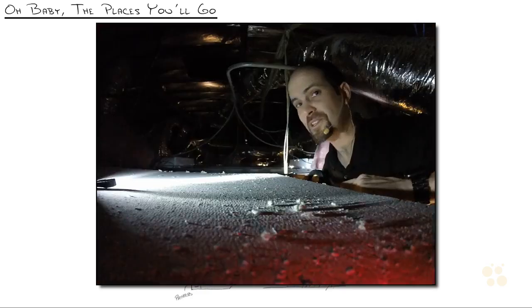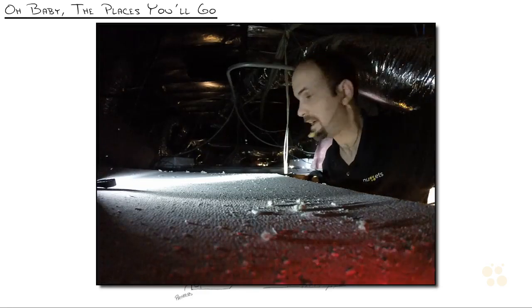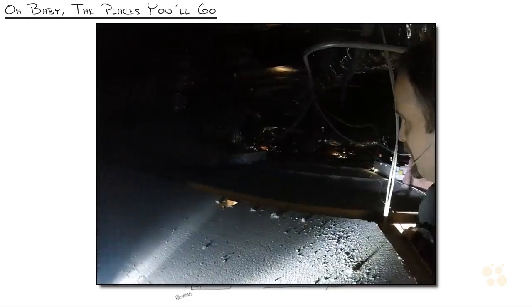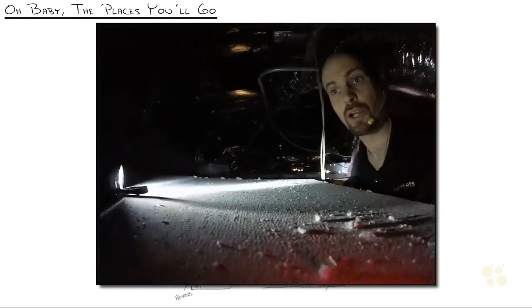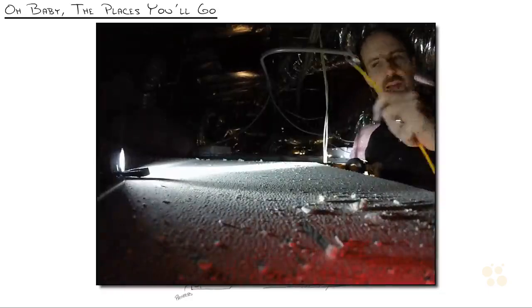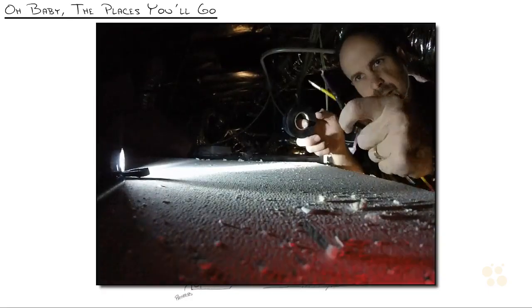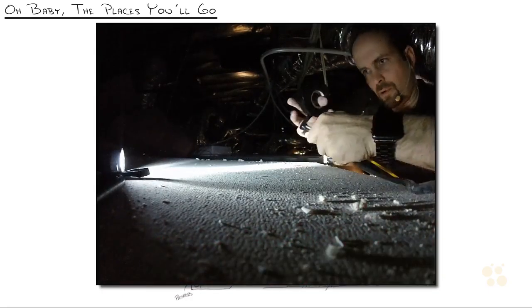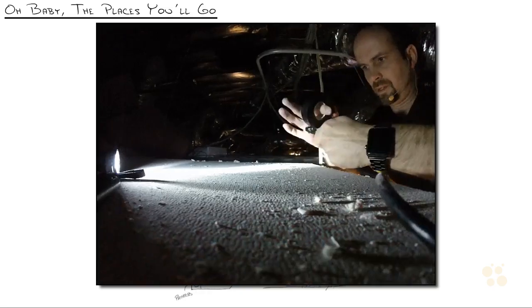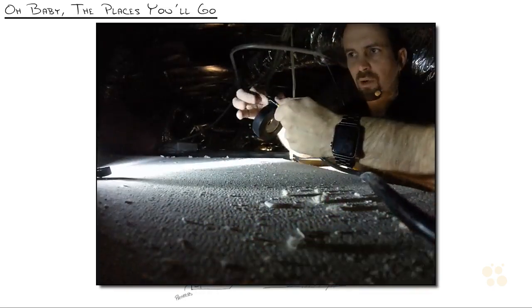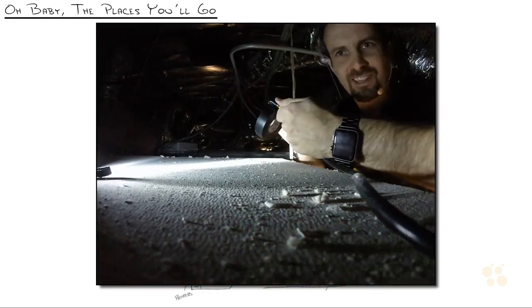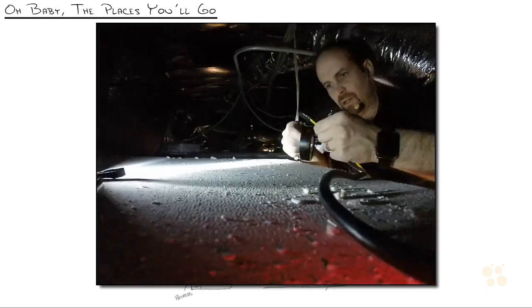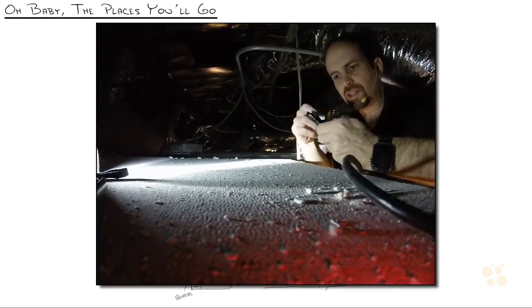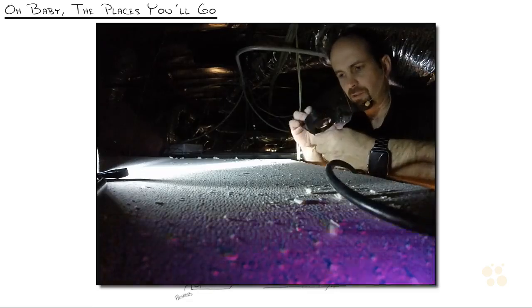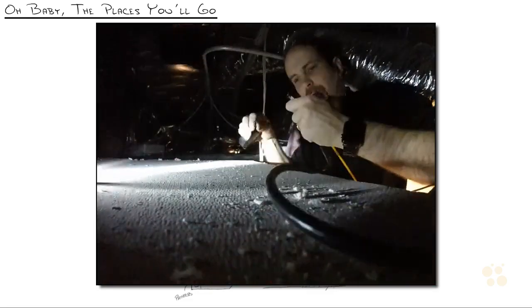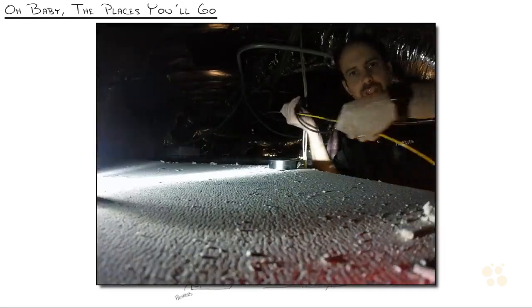All right, I'm back up in the ceiling, and I can see down there the light. I'm not sure if the camera can see it, of the ceiling tile that I moved. So now I'm going to take that fishing rod, my electrical tape, and the cable, and tape them all together. It's usually best if you try and make it a nice point right at the front. Otherwise, you'll suck in all the insulation as you go. And go down a good 3 or 4 inches on that so it doesn't pull apart as you push it through. Snap off the electrical tape and start fishing it down.